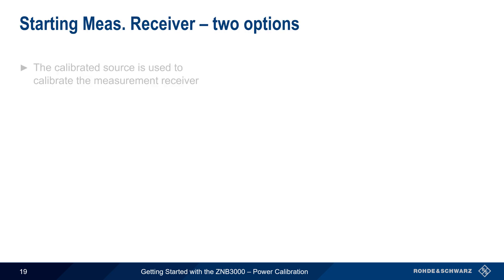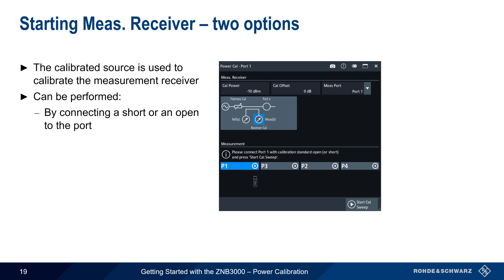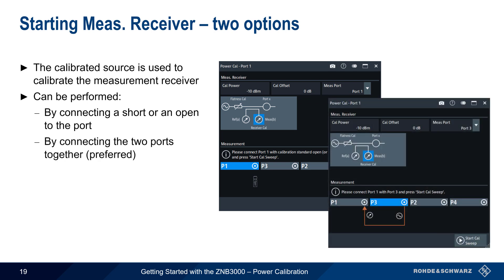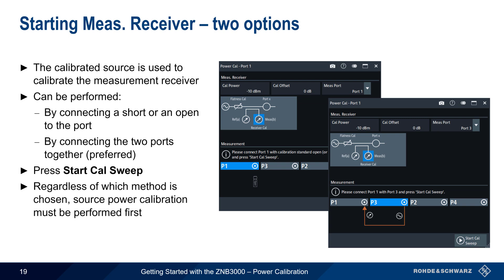A calibrated source from the reference receiver calibration can then be used to calibrate the measurement receiver. This calibration can be performed in two ways: either by connecting an open or short to the port, or by connecting the two ports together. The latter is preferred because it provides greater accuracy. Press Start Cal Sweep to begin. Regardless of which method is chosen, a source power calibration must be performed first.